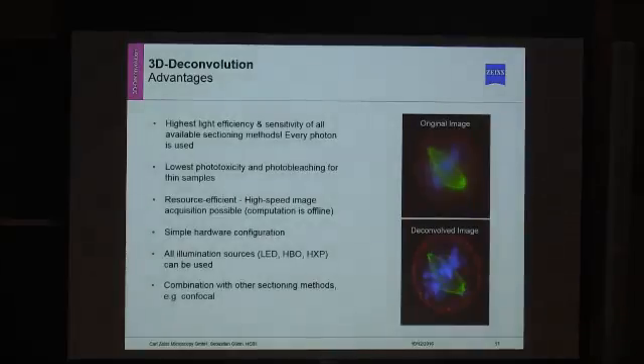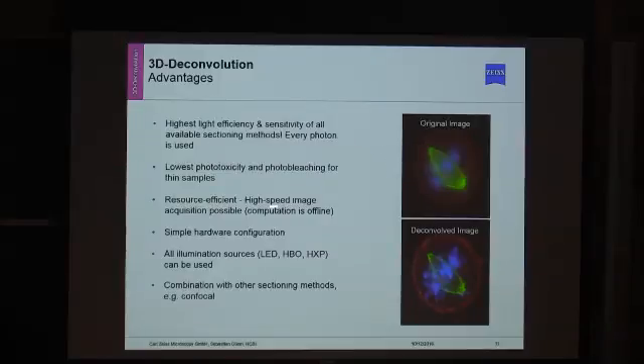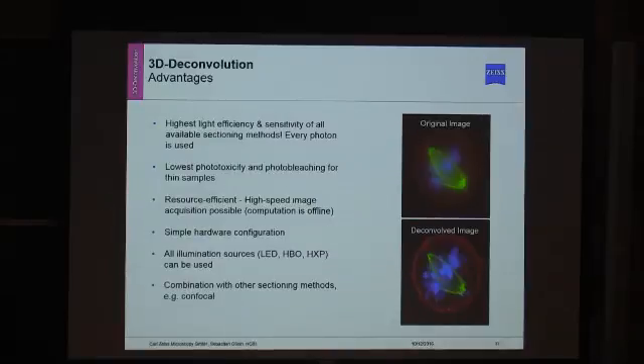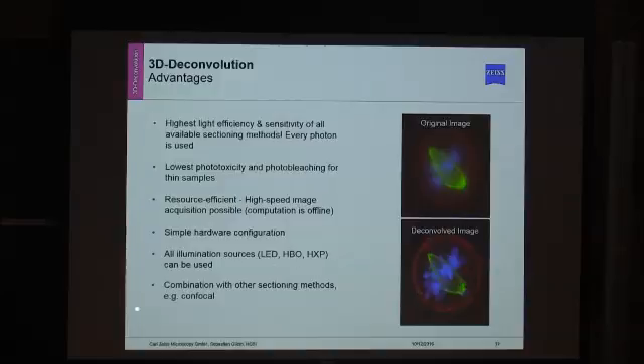One advantage of deconvolution over all optical sectioning techniques is that it offers the highest light efficiency and is the most sensitive technique, because every photon collected is actually used — you don't throw away any photons by blocking them. This provides the lowest phototoxicity and photobleaching of the sample. It is resource-efficient because you do high-speed image acquisition and perform the computation offline on a workstation, so you don't have to sit in front of the microscope. You can combine it with other sectioning methods like confocal microscopes.